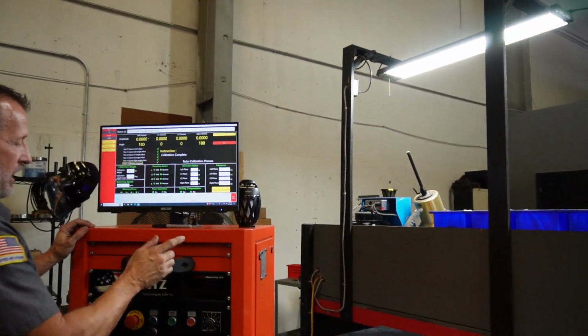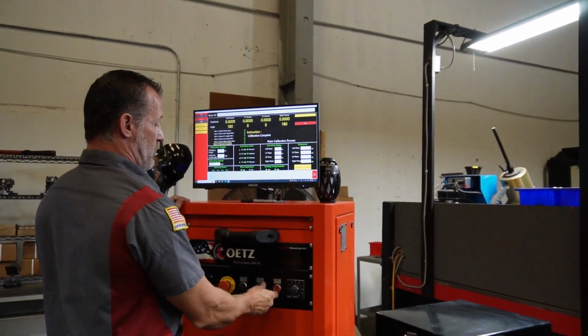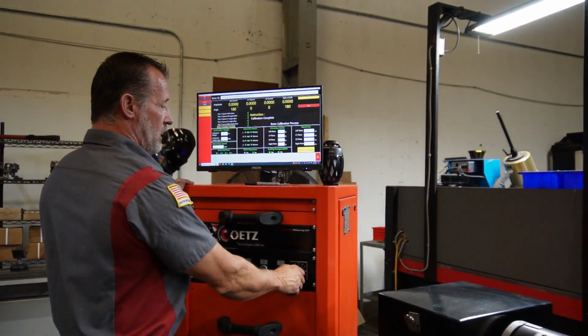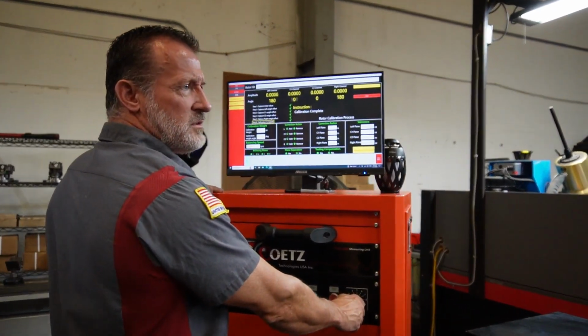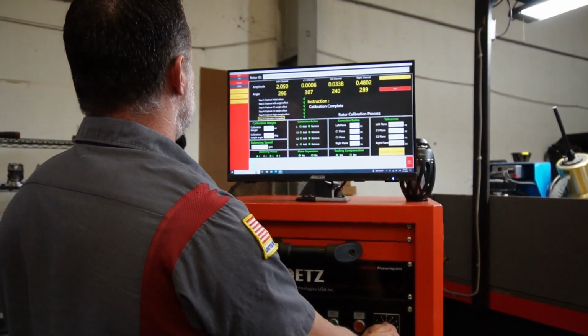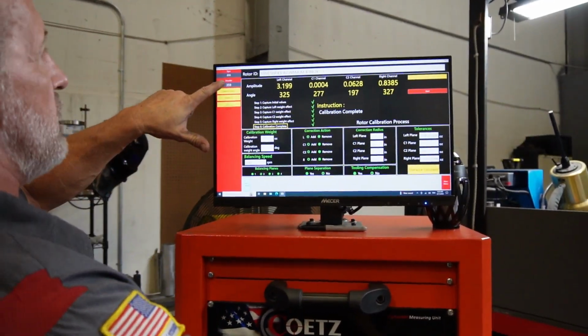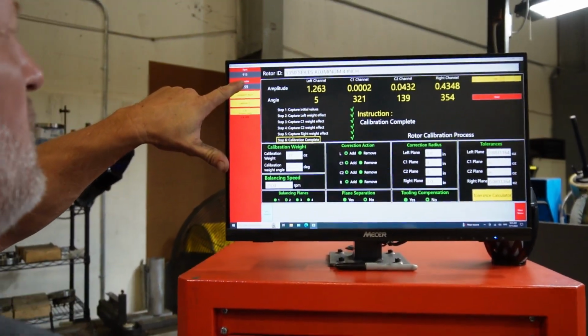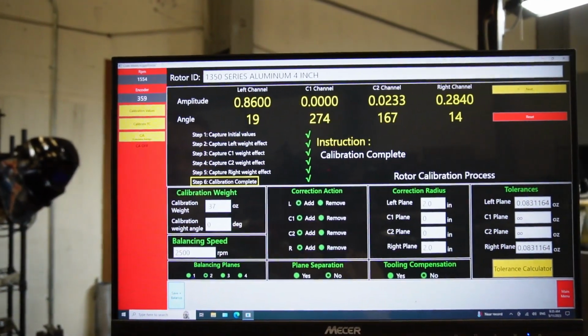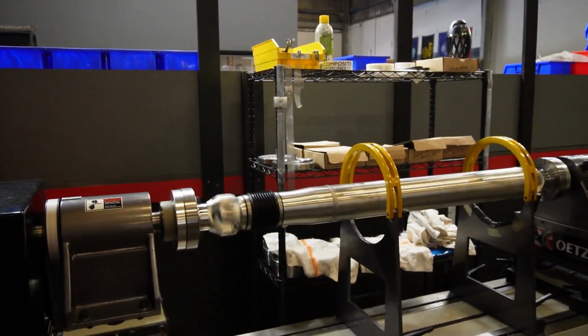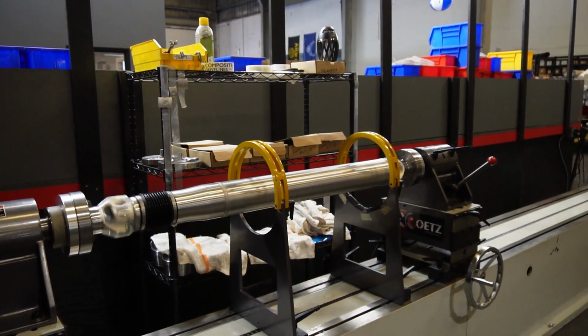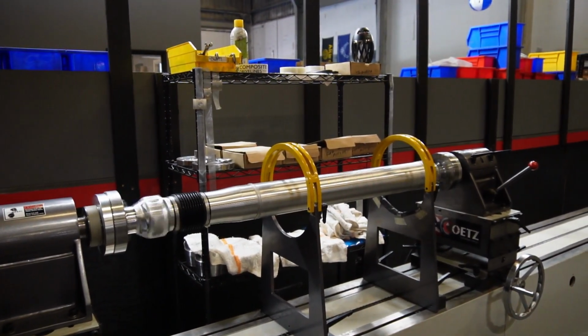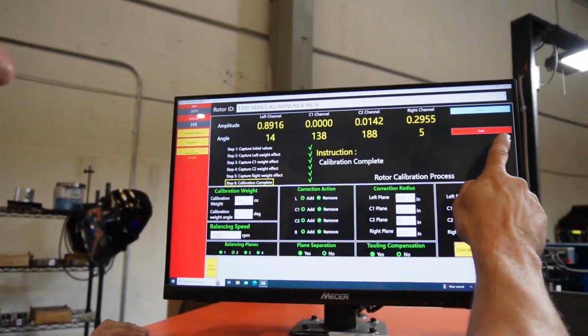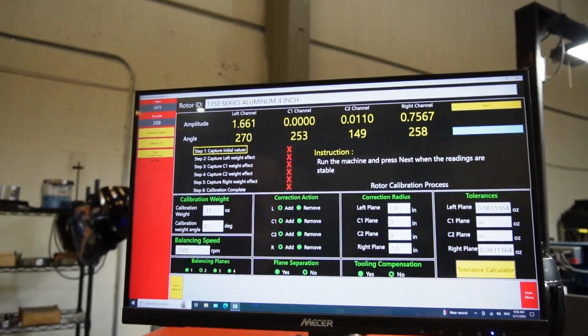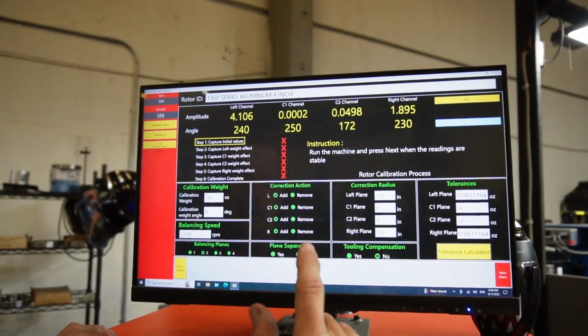So let me go ahead and start the calibration. We'll spin it about 2,000 to 2,200 RPM for calibration. Our RPM is right up here at the top corner of the machine, so I'll take that up around the 2,000 range and do an average. Watch for this number to slow down. Oh, take that back, I forgot to reset the machine. Apologize, guys.